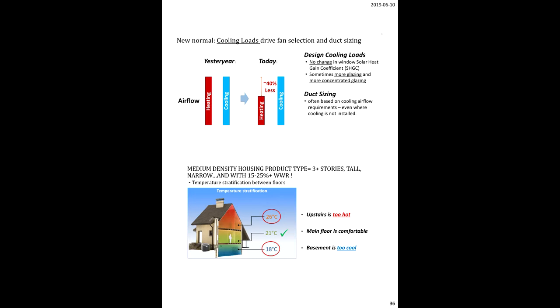The other thing to keep in mind is that low load homes, if you're principally using forced air systems, air source heat pumps, or geo systems, you have to remember you're actually moving air at a lower velocity in some cases. You might be using higher volumes over time, but you're losing velocity. And what we're finding is we're starting to get homes with lots of stagnant zones in them, areas where the air is not mixing.